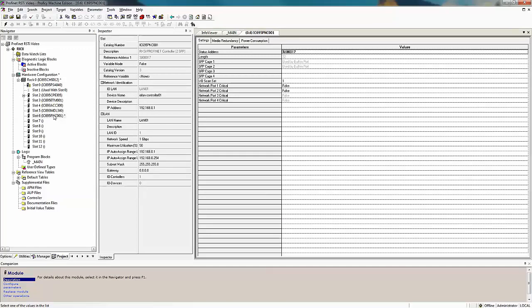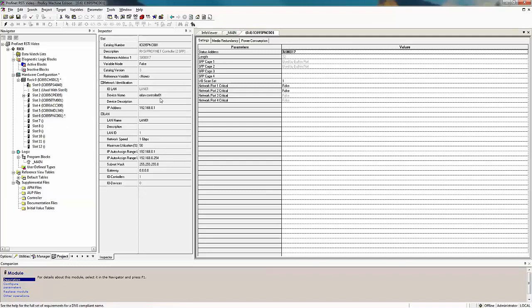Now that the module has been added, you can see the properties I have for my PROFINET controller here. PROFINET is a name-based rather than an IP address-based system. So the device name for my controller is going to be IOLAN-controller-01. If you had multiple controllers, it might be 02 for example. You can see that the range of IP addresses served up by this controller to the associated devices start at 192.168.0.1 and go to the 254 address range.